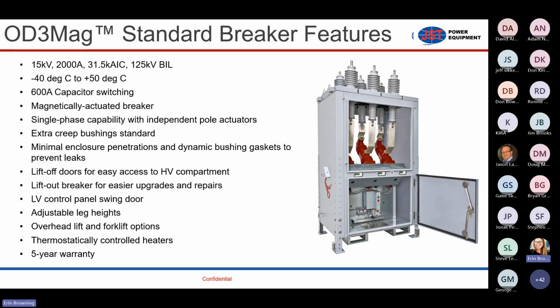The legs in this image are completely compressed. They can be extended up to 33 inches. And then we have forklift sleeves here on the front. So this breaker can actually be moved around site using a forklift. Overhead cranes are typical for handling outdoor breakers. So we have lifting eyes up top on the roof that are welded here. But to make things easier, we're allowing customers to use forklifts.